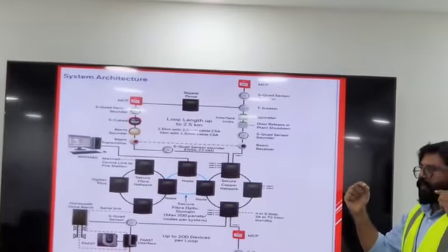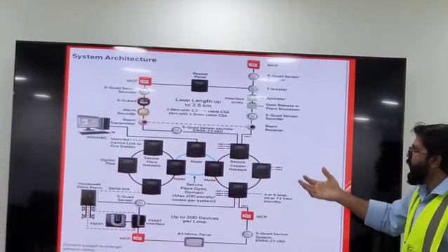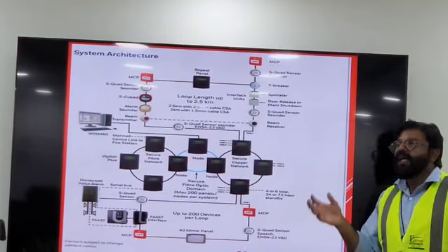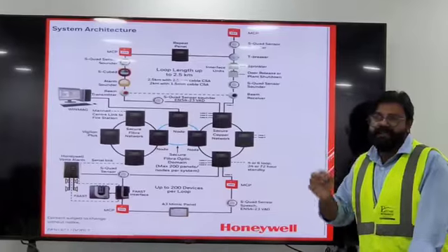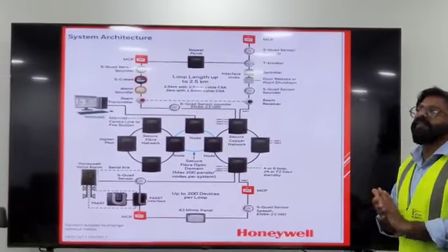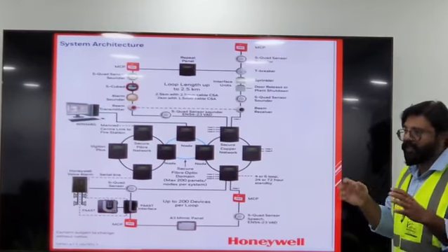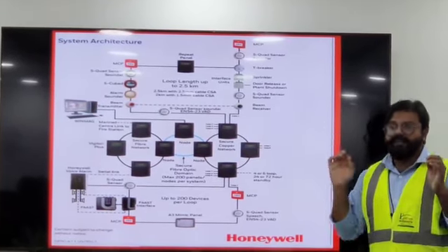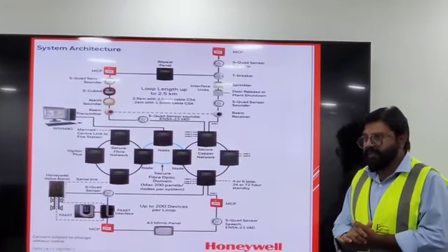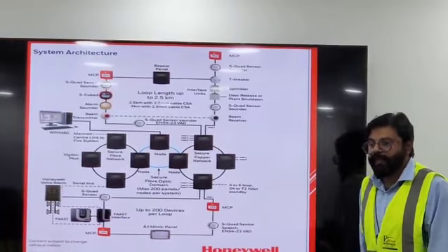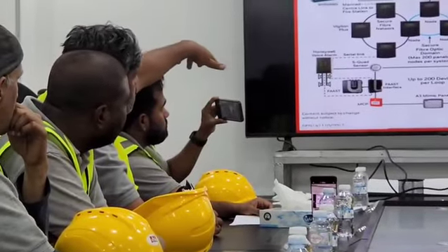The transmitter transmits the signal, and the receiver receives the signal. If the transmitter is sending the signal and the receiver is receiving 100% of the signal, it means the environment is clear. There is no fire or dust or anything, so it gives you a normal condition. When there is a cut in the signal, for example 50%, the transmitter and receiver depend upon the atmosphere.